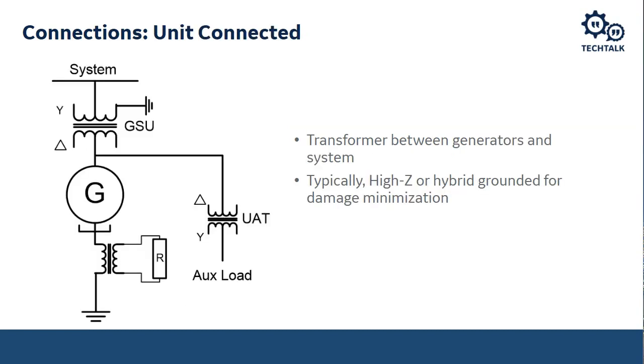So this is the typical generator installation, especially for medium to large generators: the unit connected. A generator is connected to a generator step-up transformer, which is a delta on the generator side, so it's ungrounded on the generator side, and a grounded Y on the system side. So our system side is a grounded system. However, on our generator side, it's an ungrounded system. And then we introduce a grounding transformer to make that ungrounded system a high impedance grounded system for damage minimization and for continuous process uptime. So if you do have a ground fault here, we can continue running our process until we're ready to take that process down, or that generator down, for service to address that ground fault.